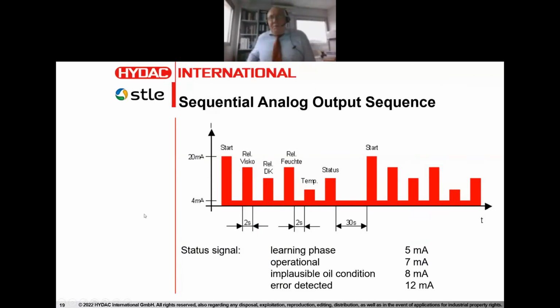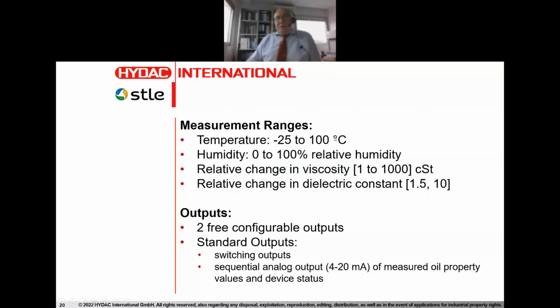The signal was a 4 to 20 milliamp signal that consisted of various components, and these could be acquired with an analog to digital converter and immediately converted online with Excel, for example, or some other software to give us the relative values. Because the sensor really detects changes, except for temperature all the other values were percent of change, or relative humidity, which was absolute relative humidity, but the viscosity and dielectric constants were relative. The temperature measurement range is -25 to 100. So essentially for any industrial system, humidity 0 to 100%, relative change in viscosity 1 to 1,000, but we're talking about percent of change.